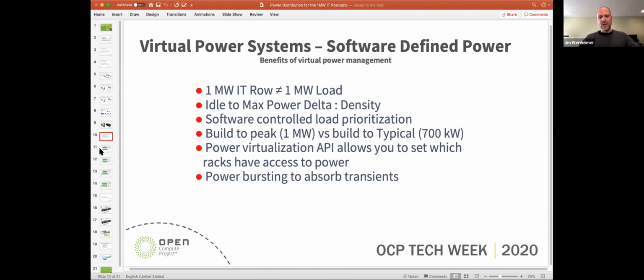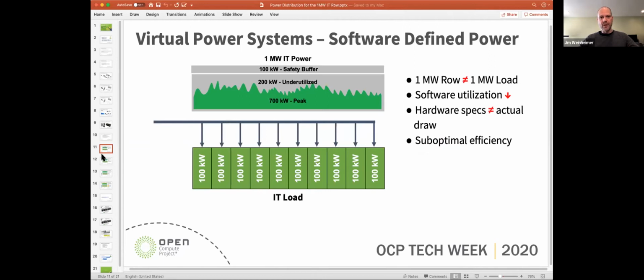There's many good reasons that we're doing that, but we can get closer by using software-defined power. On the next slide, you'll see the typical case where the actual loads are lower than the design specs. The infrastructure for a 1 megawatt row is going to be expensive, and you want to be able to use all the capacity that you've purchased.